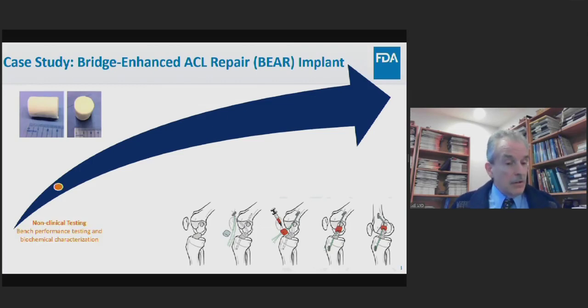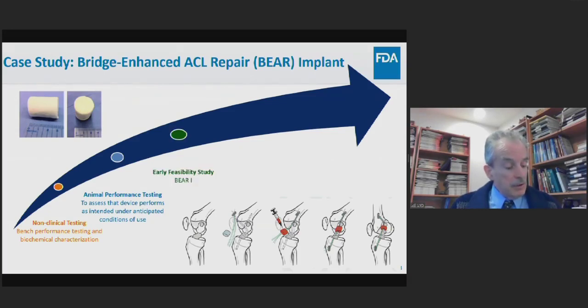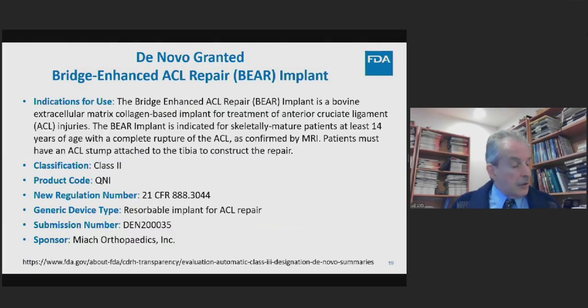During the development of this device, FDA engaged with the sponsor at each of the key stages of product development. The device progressed from an early feasibility study to a pivotal study, and positive results led to granting of a de novo classification request in December 2020. Granting of a de novo classification request provides authorization to market the device. In addition, it classifies the device into class one or class two and creates a new classification regulation and the new device type, which is now regulated through 510(k).